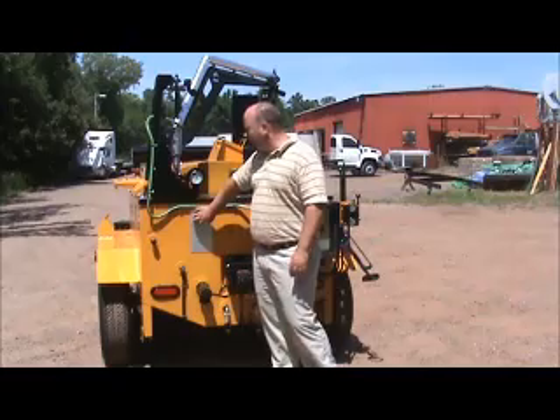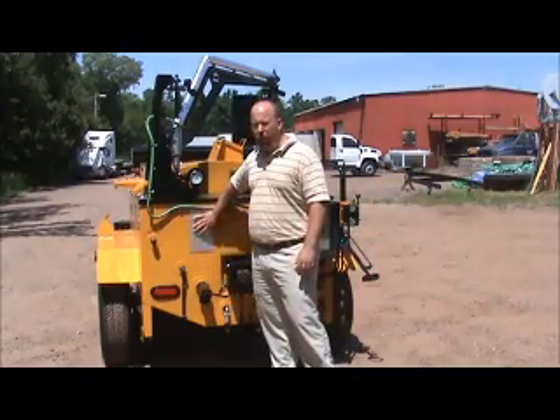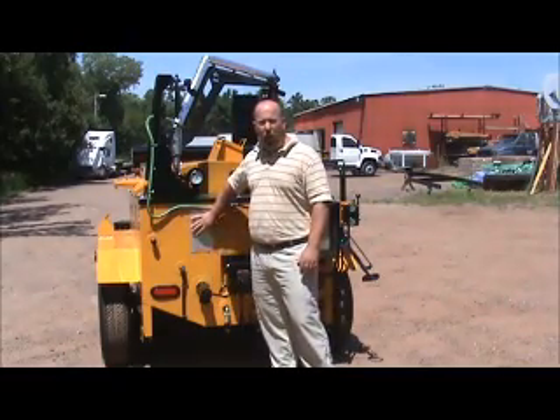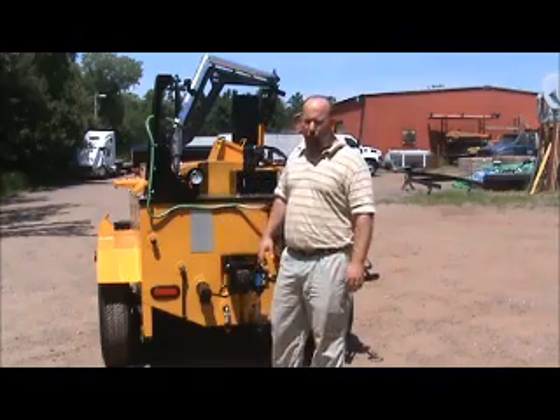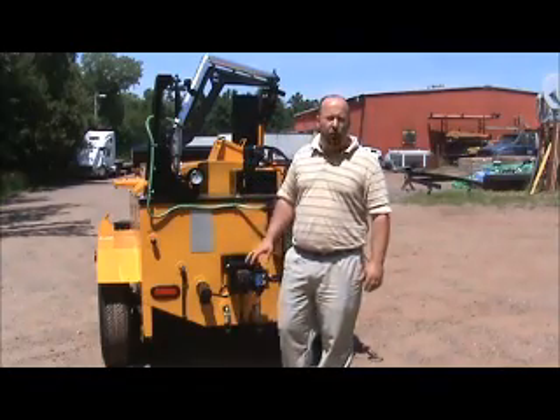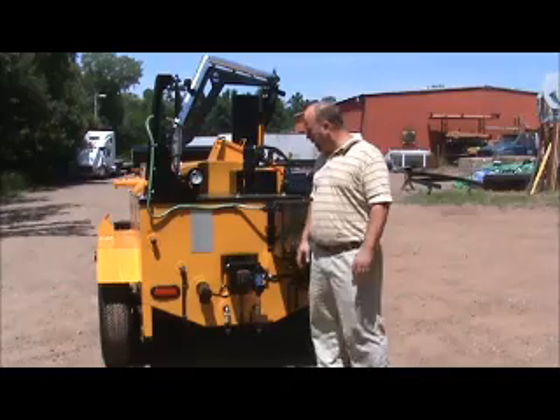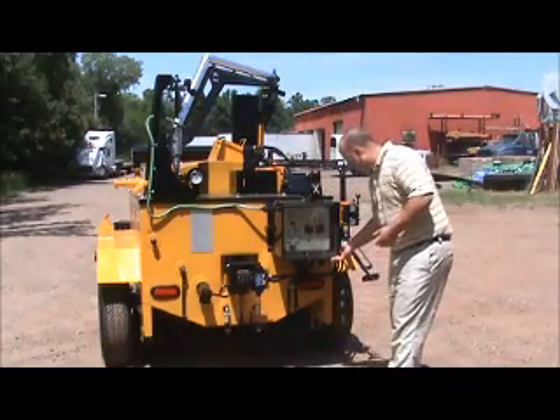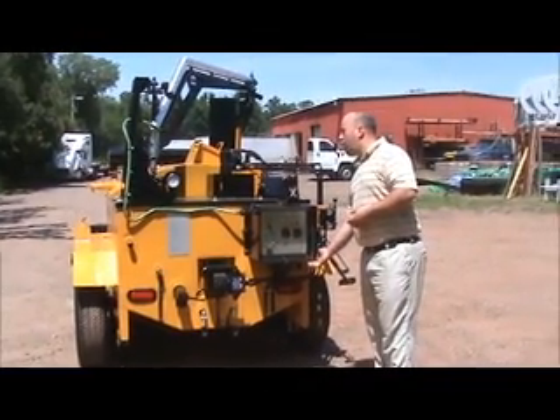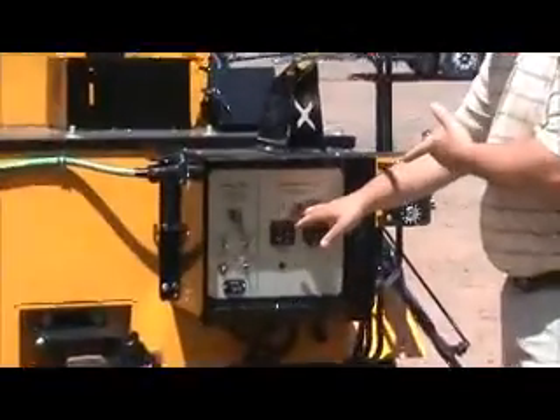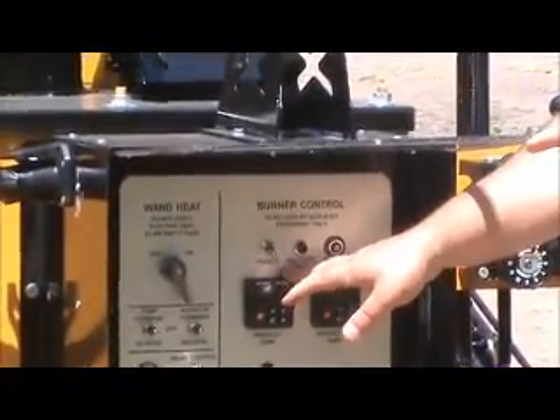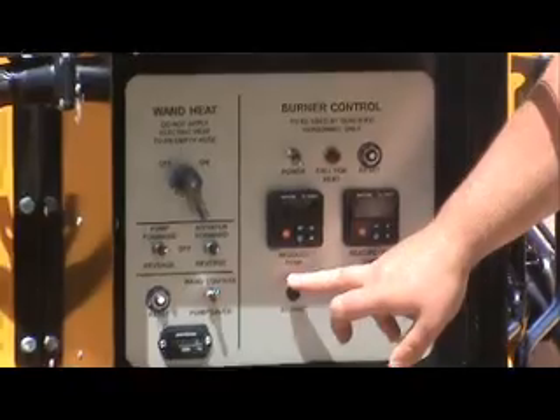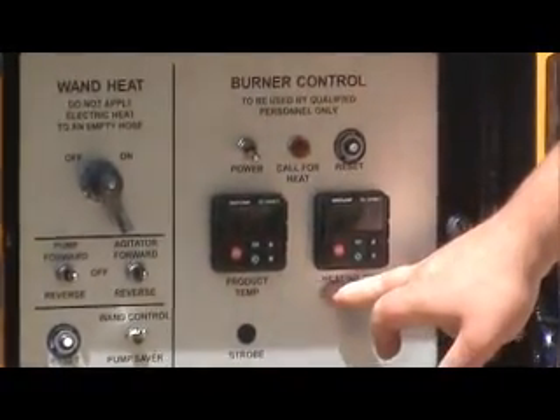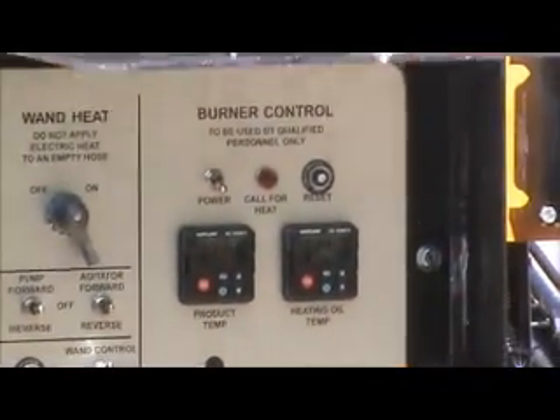This operating checklist is also in your manual. So if for some reason the tag gets covered full of tar or you lose the tag, you can refer to the manual for that startup and shutdown procedure. The last thing in the control box, which is one of the most important parts of the unit, is the thermostats for our heating system. You've got 2 thermostats. One of them is your product temperature, one of them is your heating oil temperature. Both of these control our diesel-fired burner.